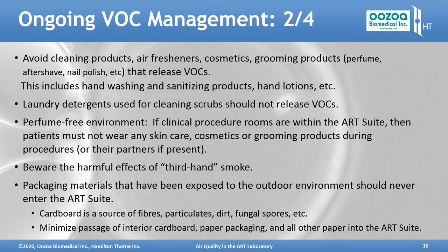Packaging materials that have been exposed to the outdoor environment should never enter the ART suite. Cardboard is a source of fibers, particulates, dirt, and fungal spores. So the outer cardboard boxes that the stuff's been shipped in should never, ever enter the lab. You can unpack those and take out the inner boxes into your entry area, or even better still, into the storeroom, and then you unpack and just take the inner packages into the clean space. So you've got to minimize the passage of interior cardboard, paper packaging, and in fact, all of the paper that gets into your ART suite.